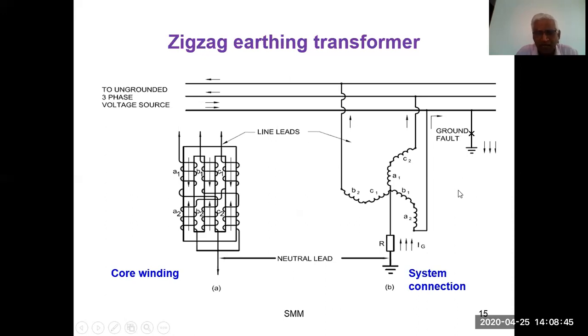Secondary is always delta connected. So whenever a phase is shorted, in the secondary one phase is missing. If the secondary is connected in delta and one phase is missing, there will be something like 64.5 volts appearing across that. So I put a relay there. My relay will give me information that there is an earth fault, but it doesn't trip.